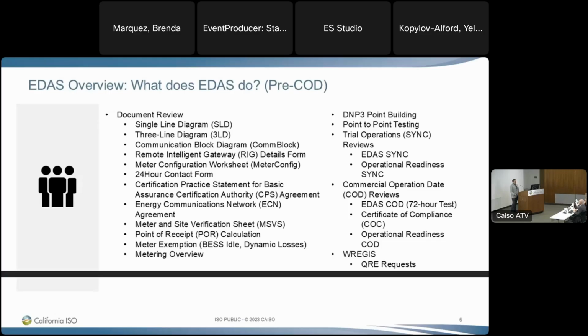And then on the right here, you can see we are responsible for the DNP3 point building. So when the single line diagram and those bucket 1 items are submitted, EDAS is responsible for creating those rig spreadsheets that get sent out to the resource owners, and also responsible for any corrections for those. We're working closely with the full network model teams to get those implemented into our EMS system. We're responsible for the point-to-point testing. Leading up to that, all those bucket 3 items get submitted and then the point-to-point test gets scheduled. EDAS is going to administer that test.